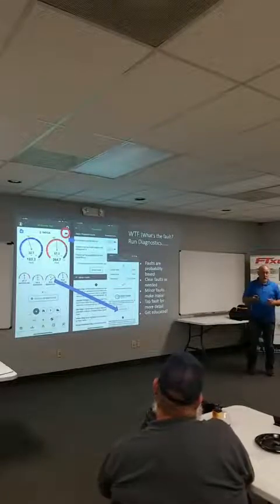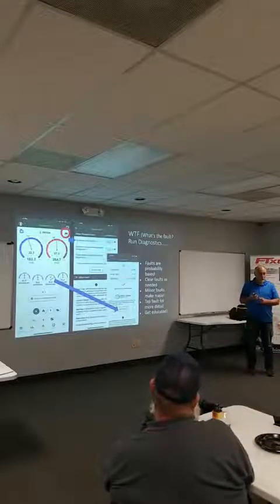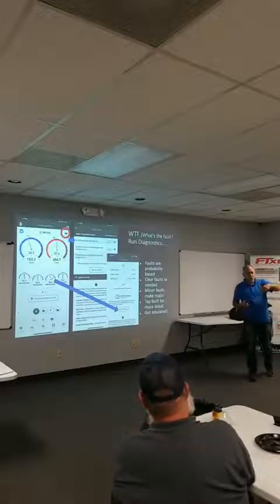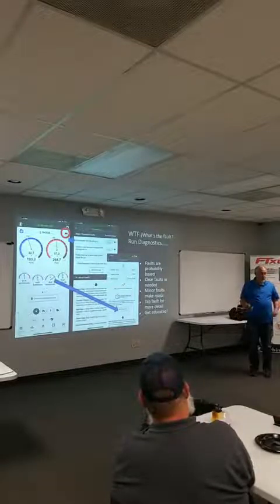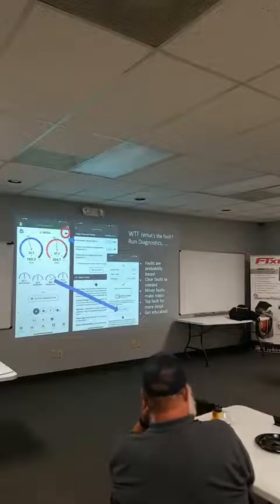They're all driven by, and think about what drives the return air temperature, or what drives the suction pressure, is your return air temp and your relative humidity. What drives your head pressure is your outdoor air temp and your relative humidity, but not the way you think. It's the relative humidity that's absorbed in the evaporator that drives the head pressure, not the relative humidity outside. Because what's the difference between the indoor coil and the outdoor coil? The indoor coil removes two things, heat and humidity. In the outdoor coil, we're rejecting all that moisture we absorbed, which drains down the drain, and all the heat that required, we're rejecting as sensible heat.